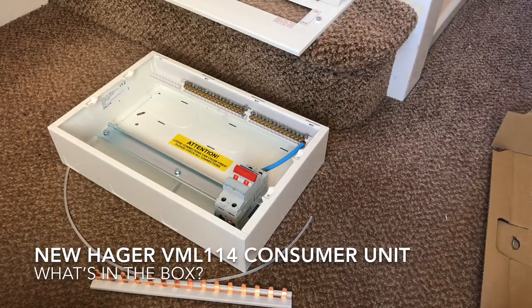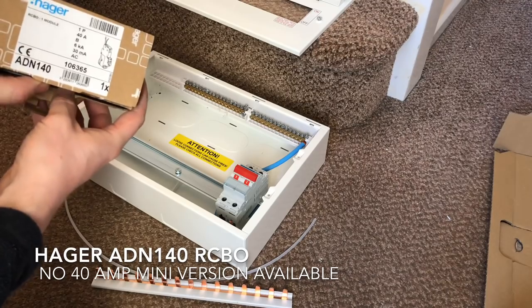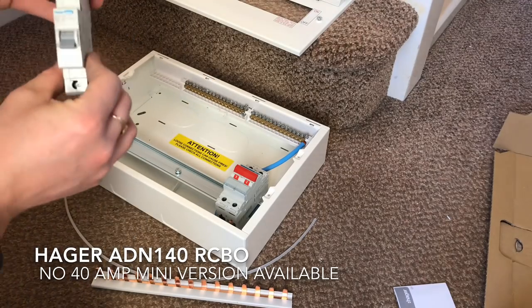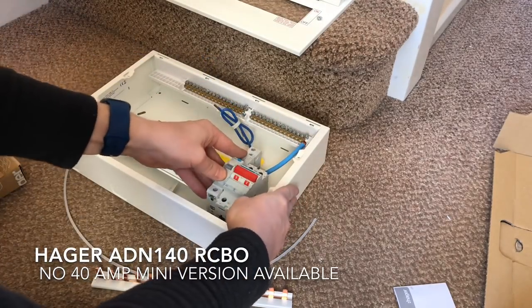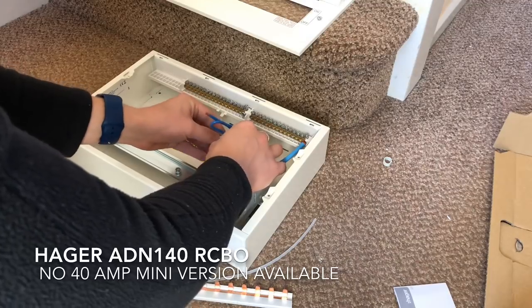That's the main switch and it comes pre-installed with the neutral tail pre-connected up to the neutral bar. I've got these RCBOs to go in the board. This is an ADN140 - it's a 40 amp, and they don't do a 40 amp in the mini RCBO type. So this is a standard RCBO size which has an earth tail as well as a neutral tail that needs to be connected.